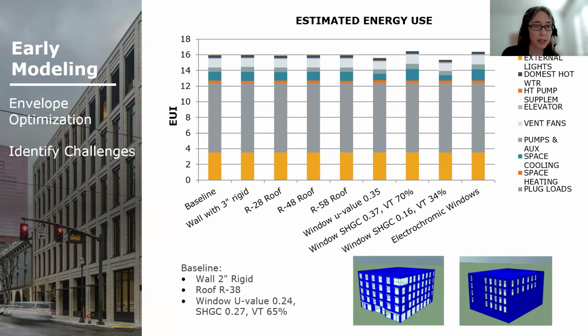During early modeling, we did a number of facade studies—this is just a sampling. This iteration has a fairly efficient baseline, and you can see a lot of these envelope options did not have a dramatic impact. The biggest levers we found were window-to-wall ratio, and of course the solar heat gain coefficient. Driving that down not only reduces energy but also impacts the mechanical system size, which then impacts cost.